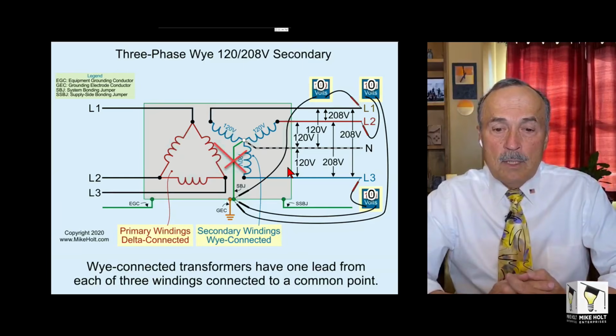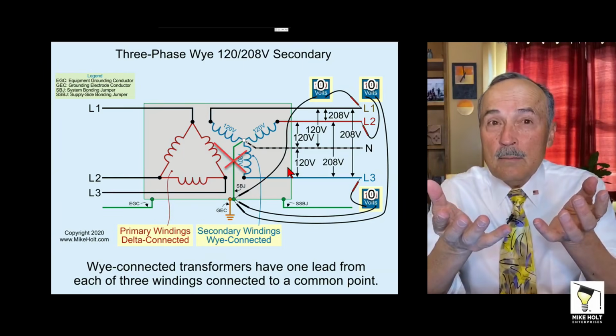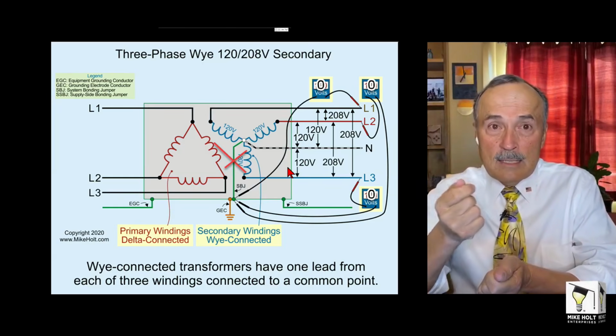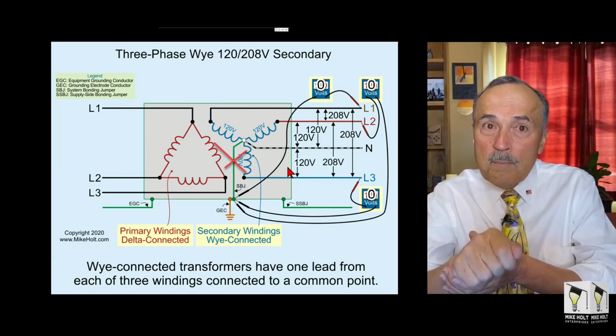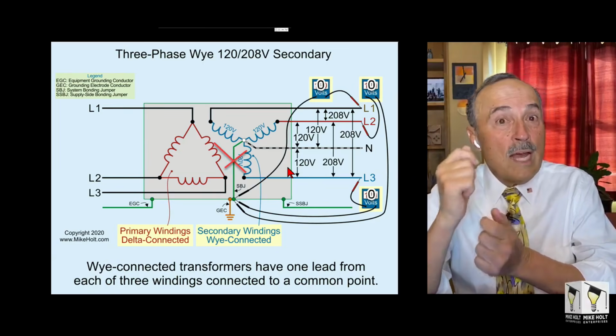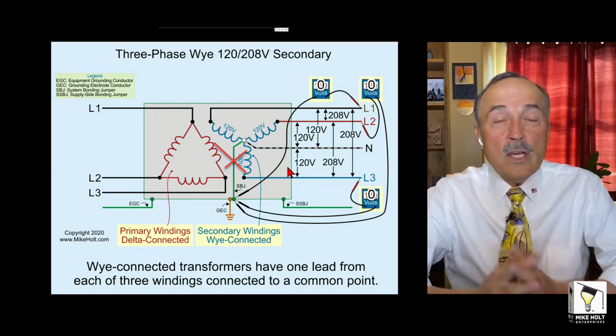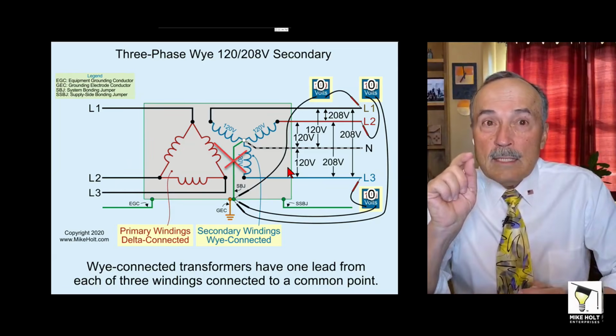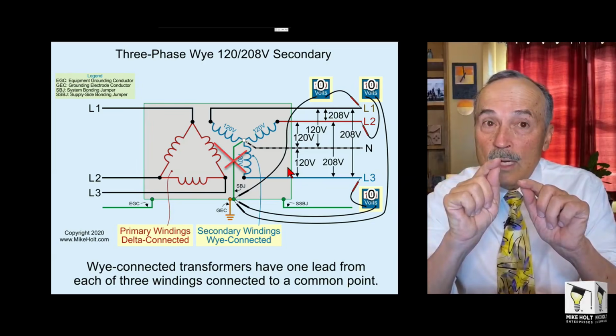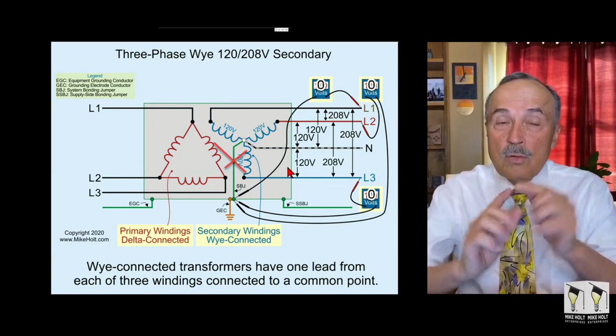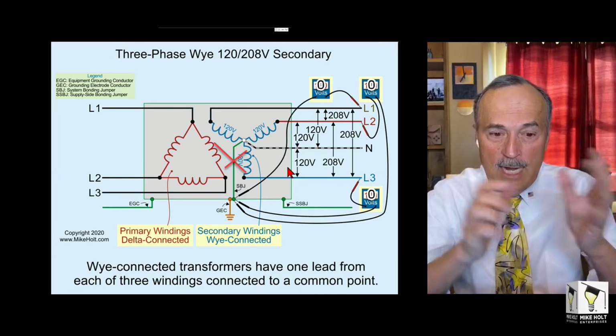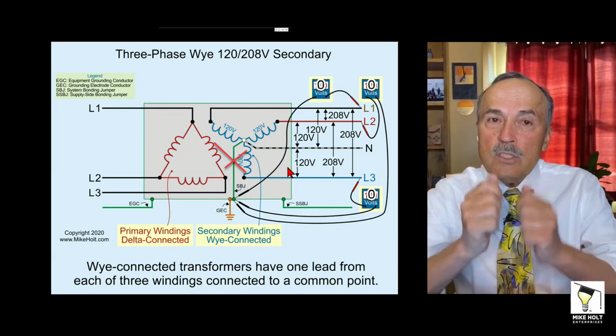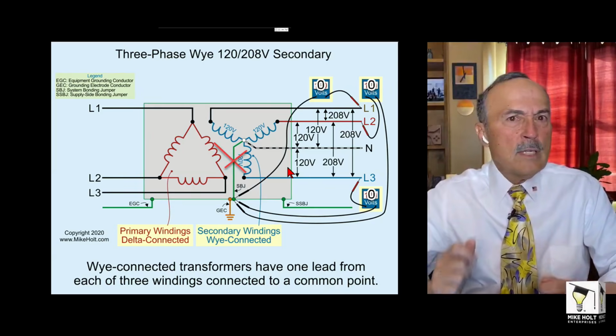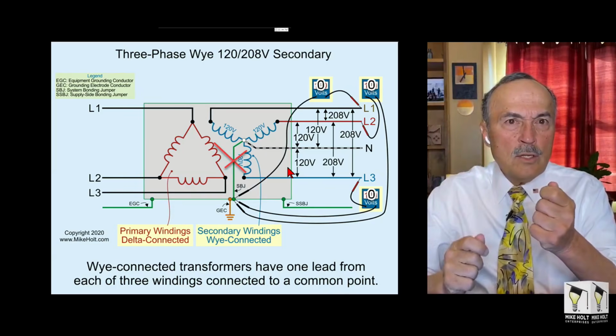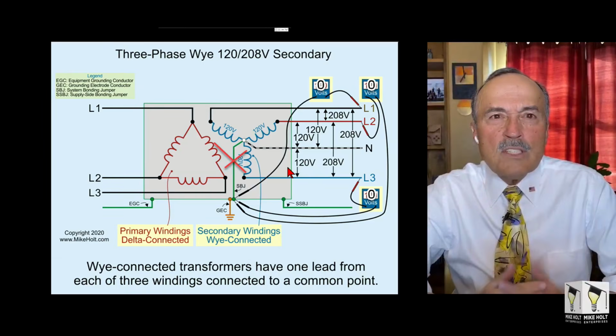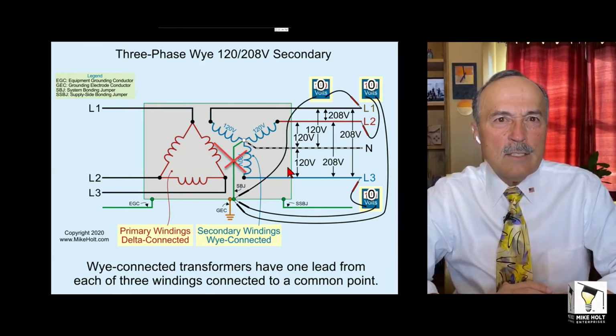Also, using this graphic as an example, if you didn't have the system bonding jumper, then it's a floating system. If you take a voltmeter between line 1 and the case, line 2 and the case, and line 3 and the case, with a voltmeter that has a low impedance setting, you're going to read 0, 0, 0. But if you go line 1 to 2, 2 to 3, or 1 to 3, you're going to see 208. And if you go line 1 to the neutral terminal, it's 120. Line 2 to the neutral, 120. Line 3 to the neutral, 120. You should be able to, with a voltmeter, and having the knowledge we've had on these three videos, get to a spot and realize, okay, I got nothing from line 1, line 2, and line 3 to the case, but I get 120, 120, 120 to the neutral, and I get 208, 208, 208. Well, guess what we have? We have a system bonding jumper that's missing. And it can create other issues, but we're not going to get into those.